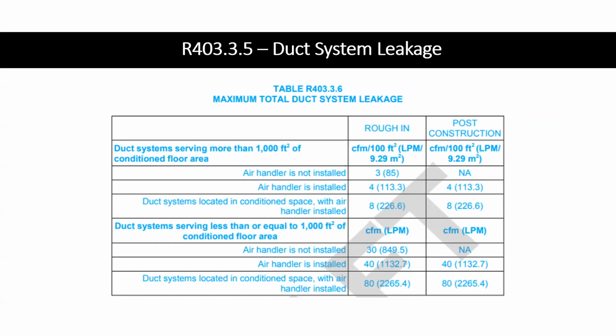So now if you look here, it says air handler not installed. If it's a rough test, 30 CFM is allowed. Not how many CFM per 100 square feet. It's just a flat 30. Air handlers installed, it's 40. And then duct systems located in the conditioned space with the air handler installed, 80. So it's allowing that so you don't have to get to that point.